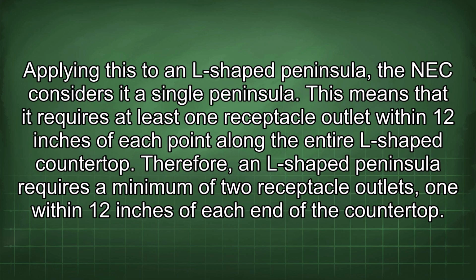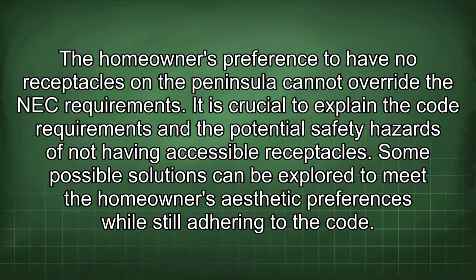Applying this to an L-shaped peninsula, the NEC considers it a single peninsula. This means that it requires at least one receptacle outlet within 12 inches of each point along the entire L-shaped countertop. Therefore, an L-shaped peninsula requires a minimum of two receptacle outlets, one within 12 inches of each end of the countertop. The homeowner's preference to have no receptacles on the peninsula cannot override the NEC requirements.